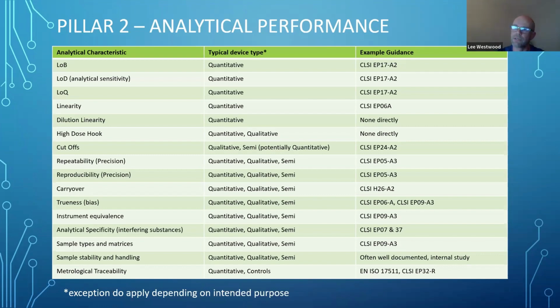But down the left-hand side here is all the analytical performance characteristics that I've come across. Some of them are not actually specified in the IVDR, but are expected. For example, metrological traceability, sample types and matrices, sample stability and handling, instrument equivalence, high dose hook effect. These are all something that you should really consider when you're outlining your strategy for analytical performance.